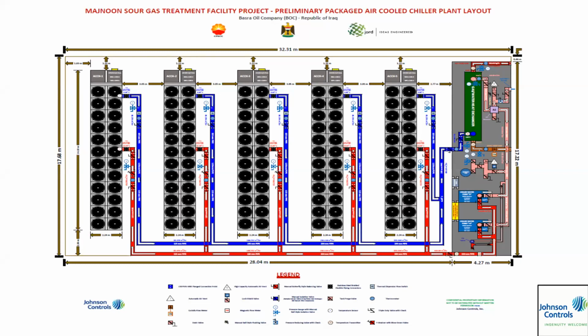And then the last one, because we talked about sour gas treatment, this is one in Iraq we did. In this case, we got five, I think these were 500 ton. No, I'm sorry, these were 400 ton chillers. And in this case, we had a custom skid we put together. On this skid, we had 2 evaporator pumps. We had all the hydronic specialties, and then we had a gas to water heat exchanger.